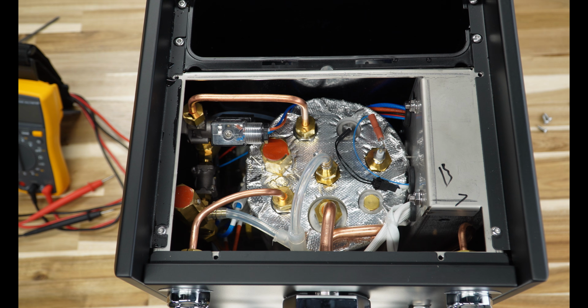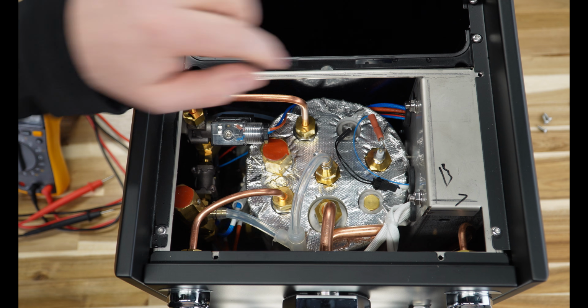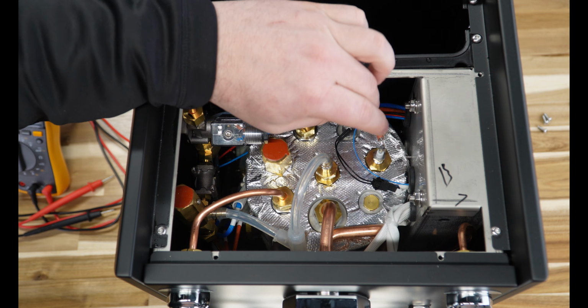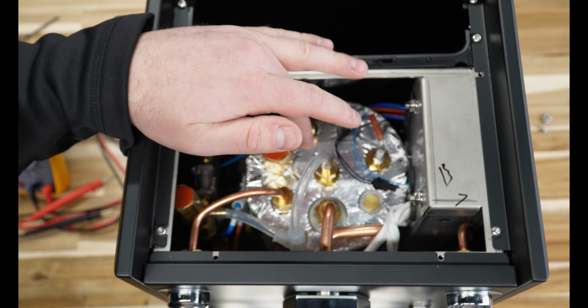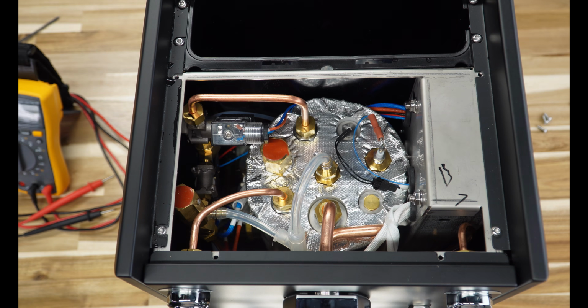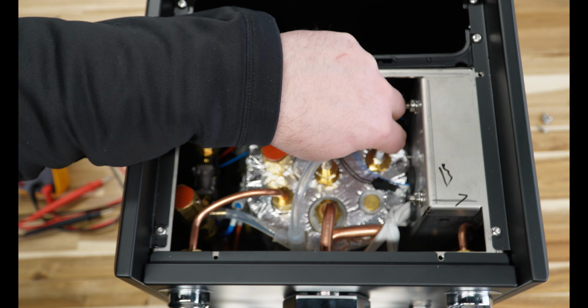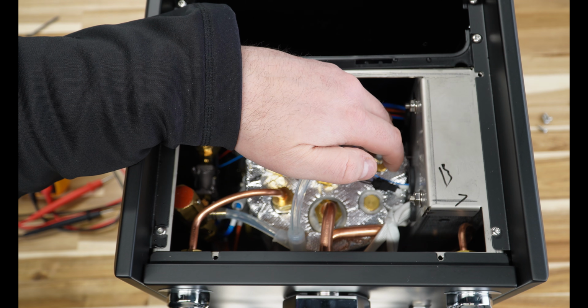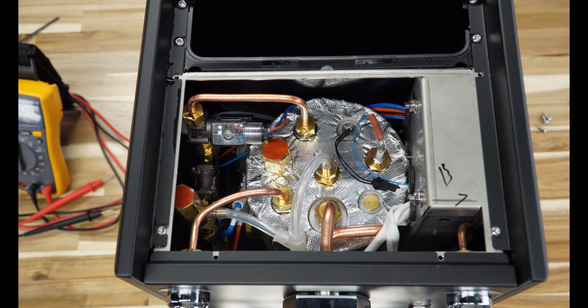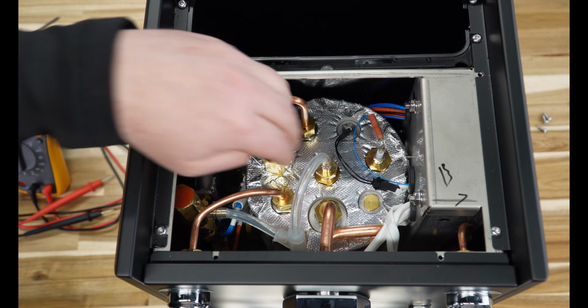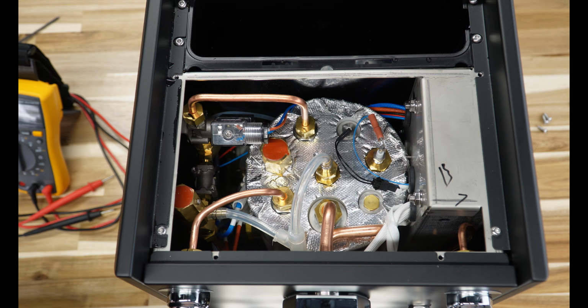So issue number one that we hear sometimes is, my boiler is not filling up, or it's overfilling, and my machine isn't working properly. So the first probe is this probe right here. The way that it works is it makes some continuity between the water and the frame of the machine. So when this gets a small amount of current through it, it knows that your boiler is full. Similarly, if you were to pull some shots, the water level begins to drop inside your boiler, and then it knows to refill your boiler.